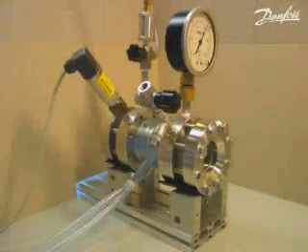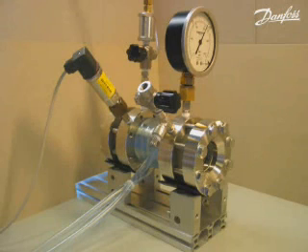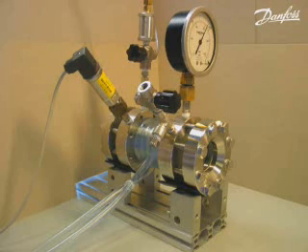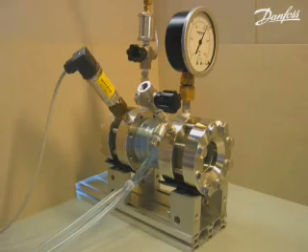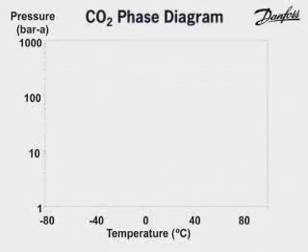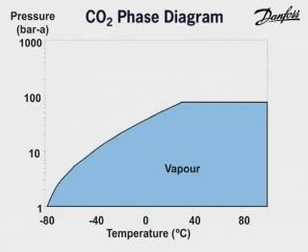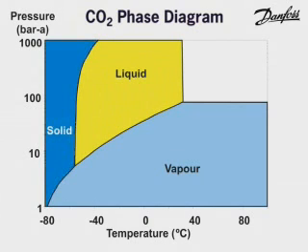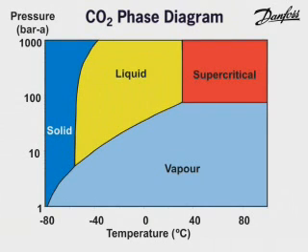In order to observe the CO2 phase changes, an observation cell specially designed and constructed by Danfoss has been used. The cell is designed to withstand pressures up to 140 bar gauge. In this diagram, the coloured areas define the temperature and pressure limits at which the CO2 vapour, liquid, solid and supercritical phases exist. This is known as the temperature-pressure diagram, or phase diagram, for pure CO2.